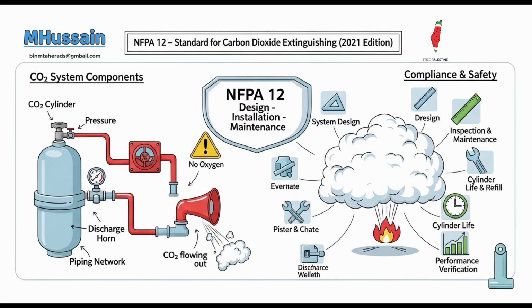Right. These tests are comprehensive. They verify that all cylinders open, CO2 flows correctly from every nozzle, and time delays, alarms, and interlocks function as intended. For total flooding, they confirm the target concentration is achieved and maintained for the required duration. For local application, they verify proper duration and coverage of the hazard. And for hand hose lines, they confirm liquid flow and pattern. The ultimate proof it works.